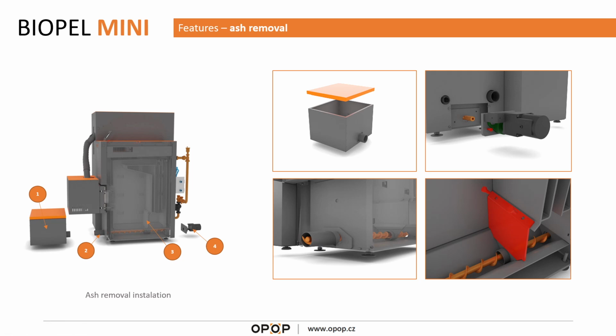Okay. Yeah, so this is simply ash removal system explained. You know, the ashes inside the ash container are pressurized, so it is not only about the volume of about the liters, about the size of this ash container. The spiral pushes the ashes inside and pressurizes them inside. So if you use ash removal system, I think, you know, for let's say 4 or 5 months, you are fine to not clean the boiler, and then after 5 months, let's say, you remove the ash container and clean it. Of course, again, it depends on the quality of the combustion. So if you have not good quality of the pellets, you will have to clean probably more often.